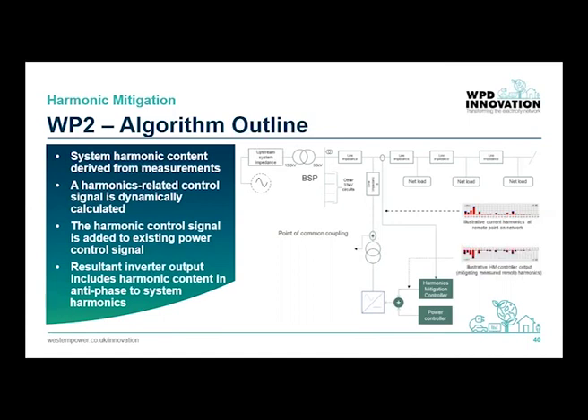These mitigation control signals are fed into the inverter controller with the conventional fundamental power control signals. As a result, the inverter carries out its normal power conversion function and has an additional harmonic mitigation output. This causes a cancellation of harmonic currents at the current measurement point and leads to reduced harmonic distortion in the upstream network.